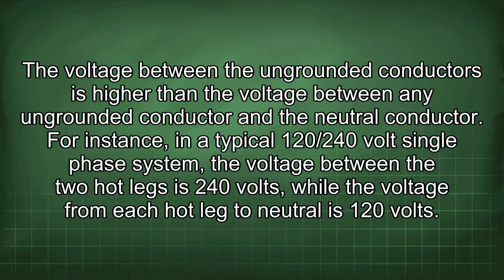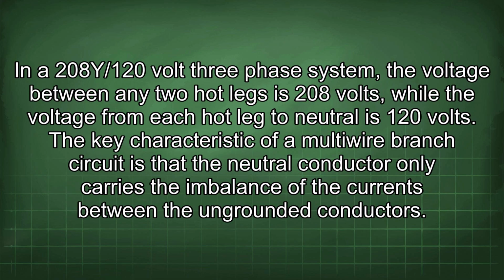For instance, in a typical 120/240 volt single-phase system, the voltage between the two hot legs is 240 volts, while the voltage from each hot leg to neutral is 120 volts. In a 208Y/120 volt 3-phase system, the voltage between any two hot legs is 208 volts, while the voltage from each hot leg to neutral is 120 volts.